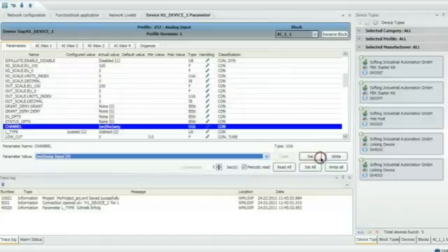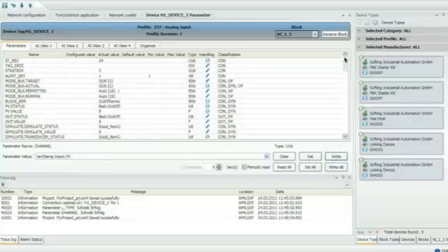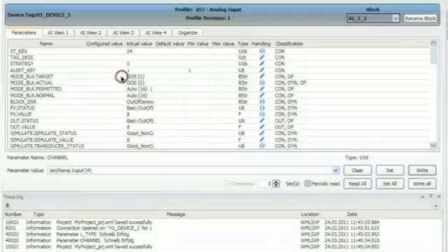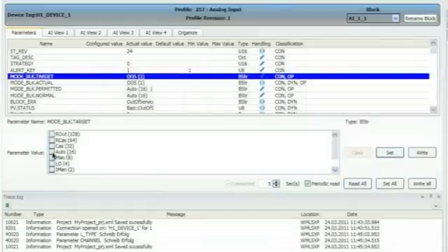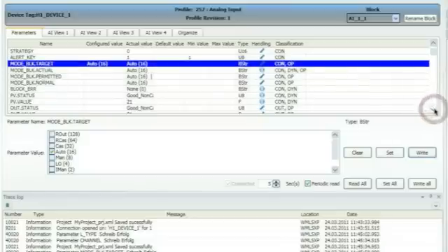L-type to direct or indirect. Channel to the value which should be published. Then set the block from OOS, out of service, to auto. To write the parameters directly online in the function block, please click first on Set and then on Write. If everything works fine, then you will see the process value.